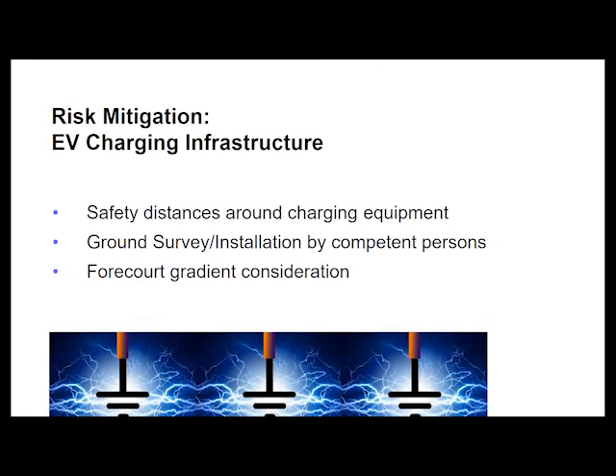On top of that, a ground survey should be conducted. It's recommended that one is carried out to assess the site's soil resistivity, how far potential current could travel, how conductive the soil is. This needs to be carried out for each site due to variances in the compositions of the soil at each different location. This allows contractors to determine the appropriate level of electrical earthing required for the charging equipment to mitigate against the risk of ground penetrating conductors potentially becoming live should there be an electrical fault. And as always, such equipment should be installed by a suitably qualified, competent person.